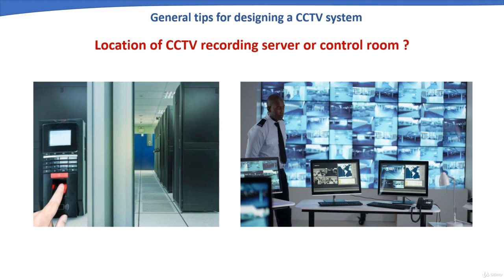The CCTV control room must be properly designed: it should be large enough to accommodate CCTV hardware such as monitors, workstations, and servers. It should be well air-conditioned since CCTV electronic equipment operates 24/7. The distance between CCTV monitors and the operator's desk should be at least 8 feet with a viewing angle of 30 degrees.